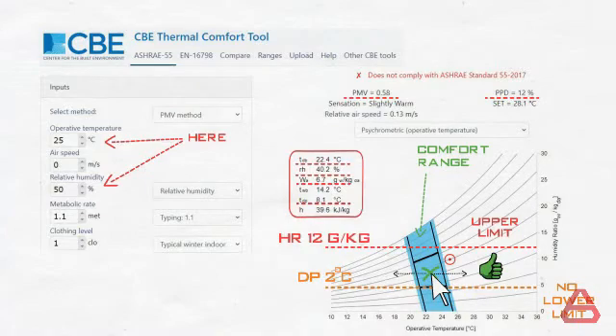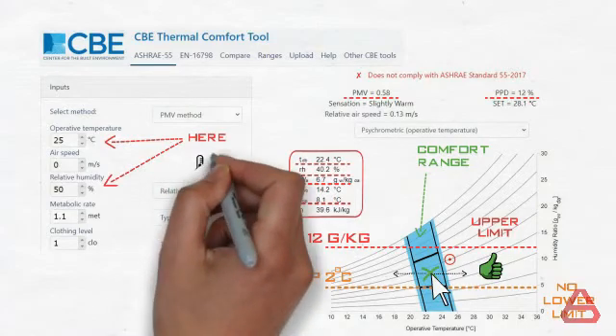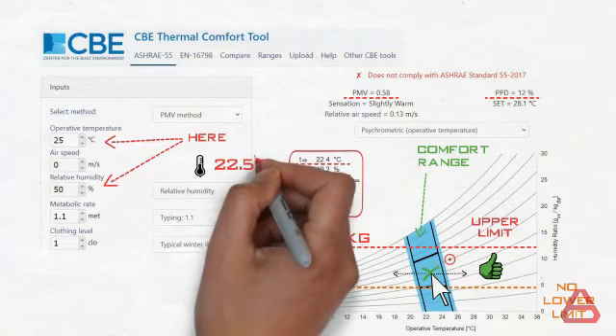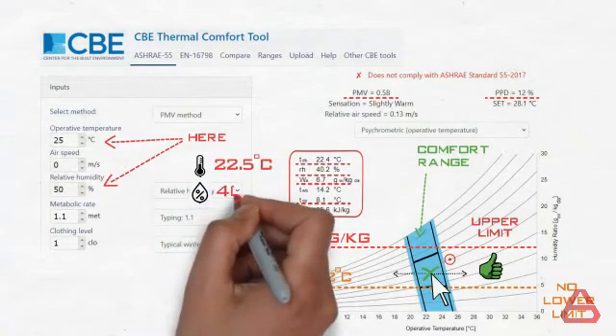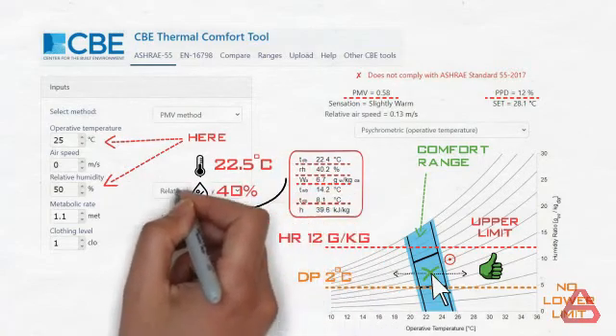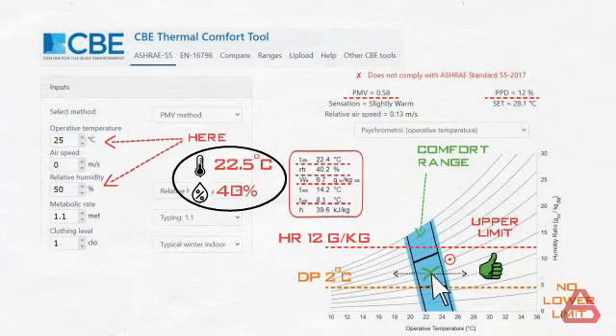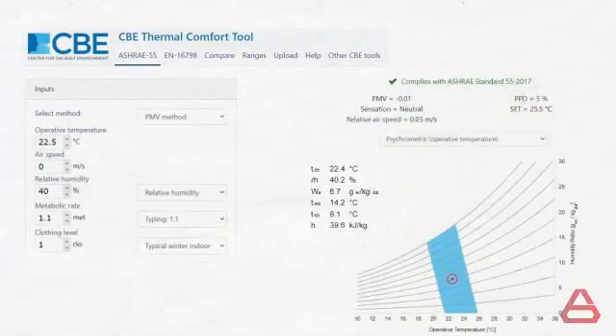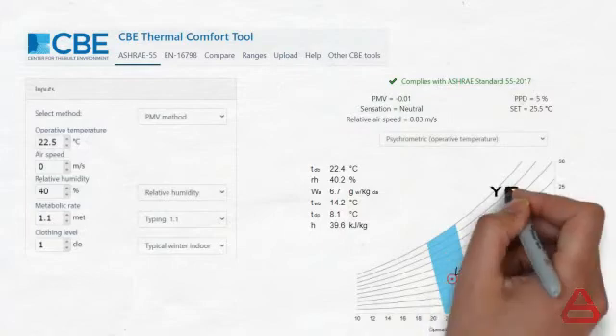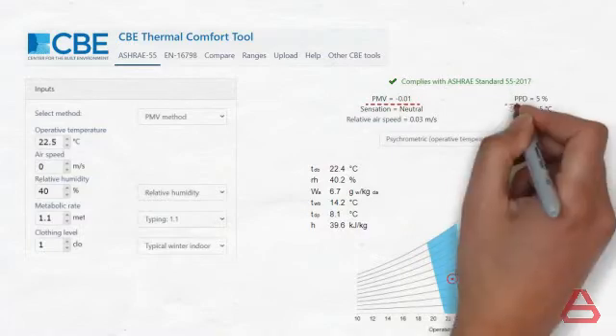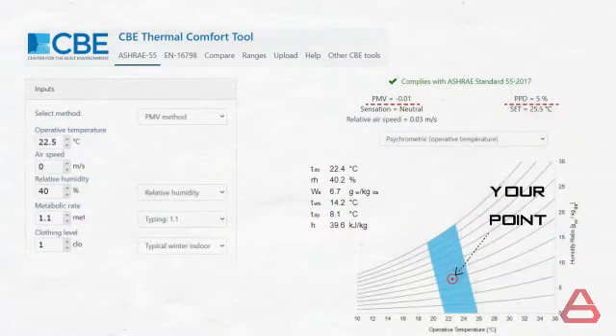So let's do as instructed. Hovering over the center returns approximately an indoor temperature of 22.5 degrees Celsius and a humidity of 40%. We record these numbers and input them back in the input section and the tool directly places your point on the chart and returns the values of the PMV and the PPD.